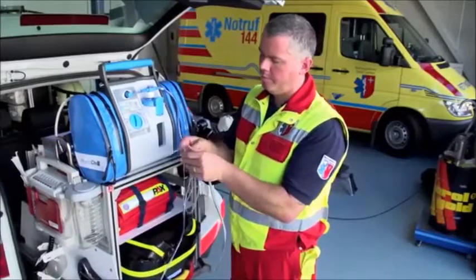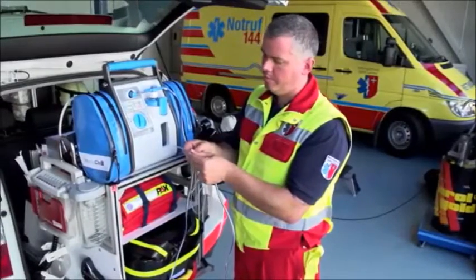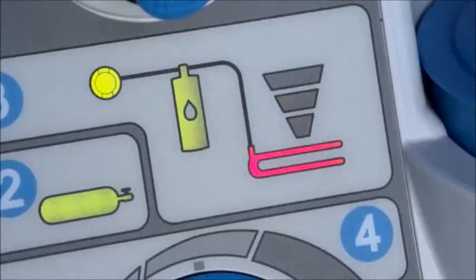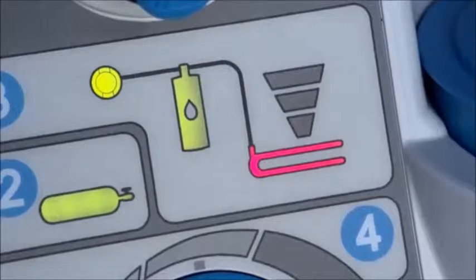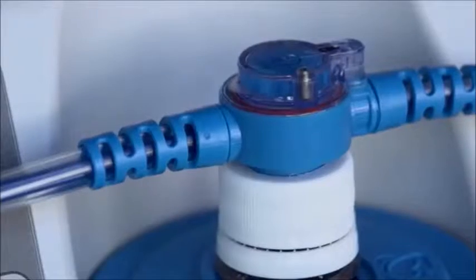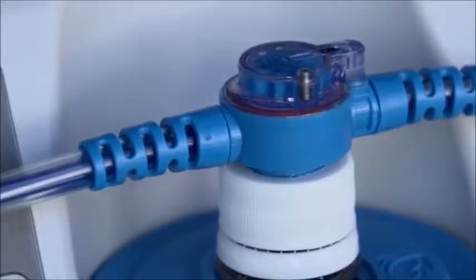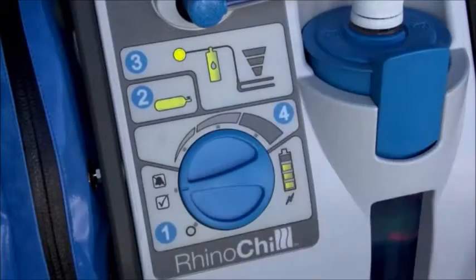Kink one of the nasal cannula near its hub to check that the overpressure sensors are working correctly and that the flow stops when the system alarms. The nasal cannula indicator light should then turn red. The flow indicator light will not be illuminated, and the flow indicator on the top of the bottle will not be moving. Move the setting control knob to check position to clear the overpressure alarm.